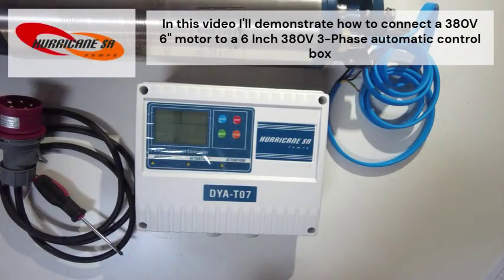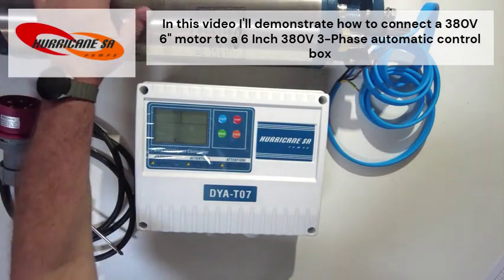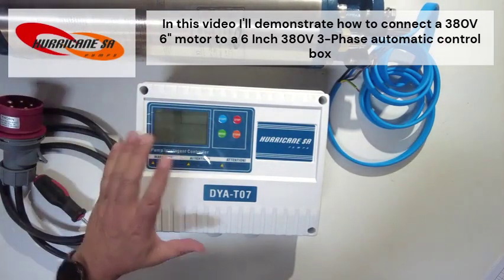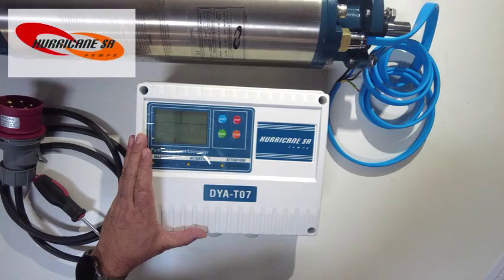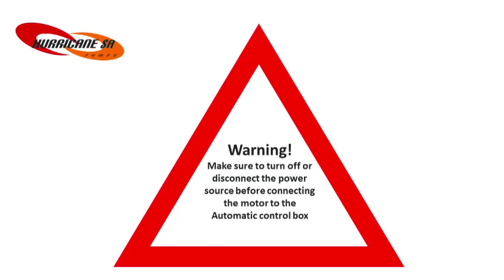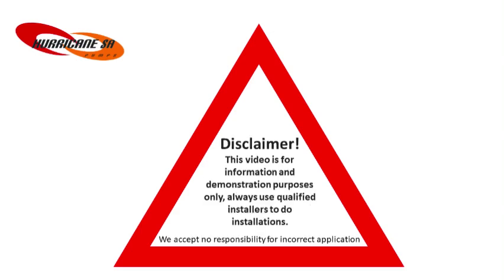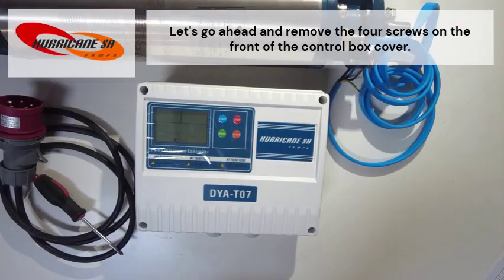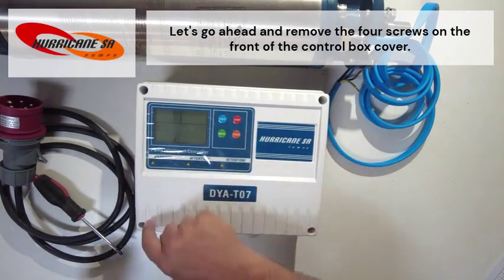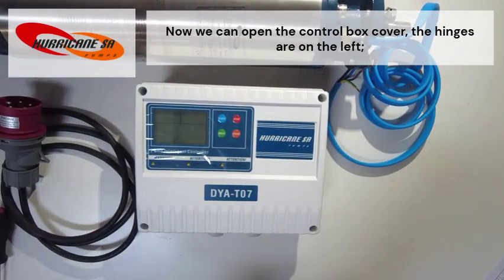In this video, I'll demonstrate how to connect a 380-volt 6-inch motor to a 6-inch 380-volt 3-phase automatic control box. Warning: make sure to turn off or disconnect the power source before connecting the motor to the automatic control box. Let's go ahead and remove the 4 screws on the front of the control box cover. Now we can open the control box cover. The hinges are on the left.